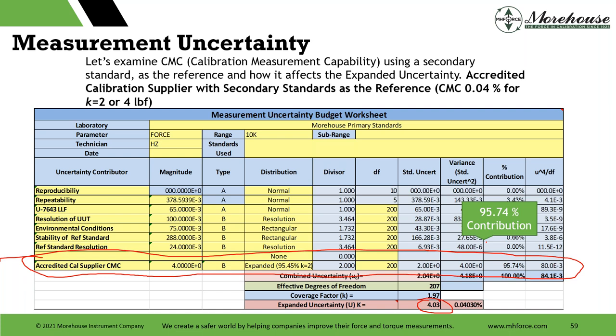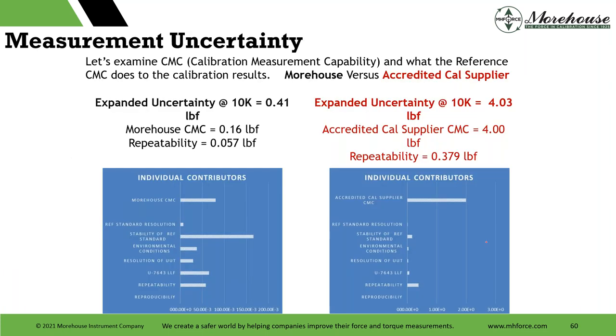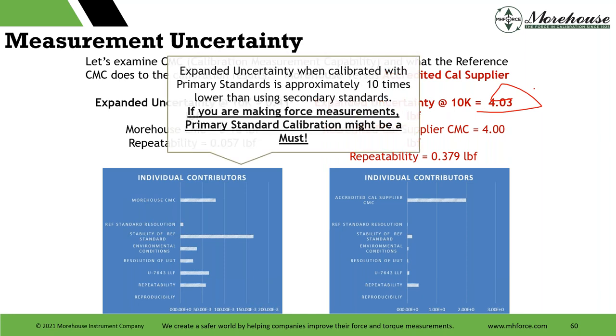If they're using the UCM with automation, that's probably going to get cut in half to like 2 pounds or less. So there is the in-between, and the in-between, between dead weight or secondary accredited supplier with a machine that does tension and compression, is basically the Morehouse UCM with automation. And without automation, you're probably going to really mimic these numbers or close to those numbers. Maybe you get 3.5 pounds uncertainty instead of 4.03.